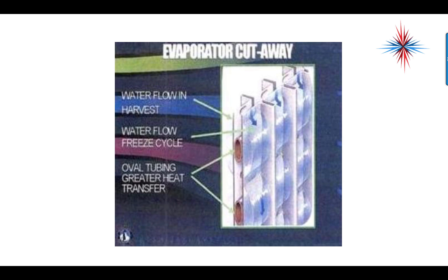If you take a look at the evaporator of any ice machine, this is a cutaway section. The oval tubing in the center has great heat transfer because it has good surface area across the evaporator plates, which are on the outside. Our refrigerant goes through the center of this tubing, removes heat from the plates, and brings the plates down to between 10 and 20 degrees. The water flows down on the outside of this and starts freezing to the plates.